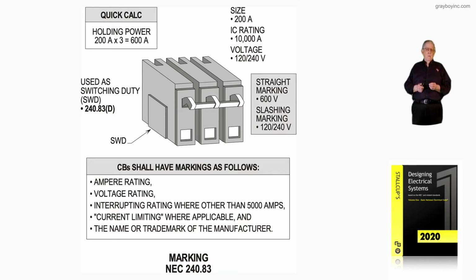Meaning what? Well, if you really looked at 240.85 of the code, it would state that 120, 240 or 277, 480 mark type breakers with the voltage rating could only be used on a solidly connected ground type system. Now, this particular breaker, as you see, is rated for switching duty. But a straight mark breaker, say 480, 600 volt, maybe 240, they could be used on any system.